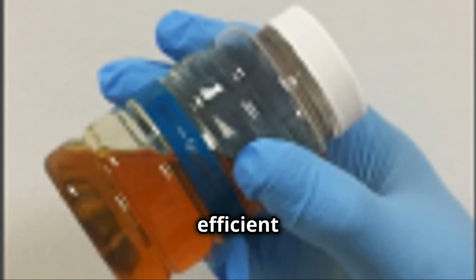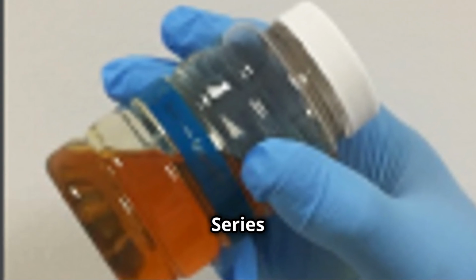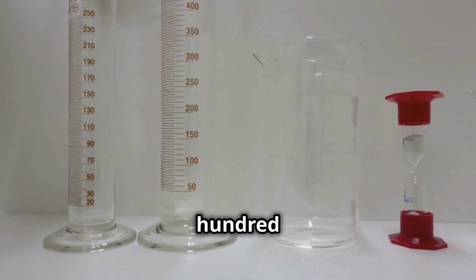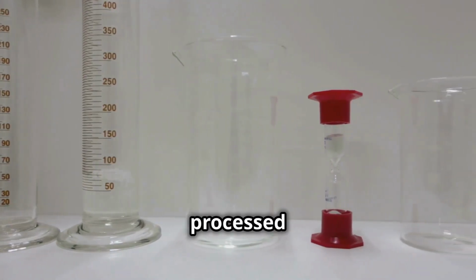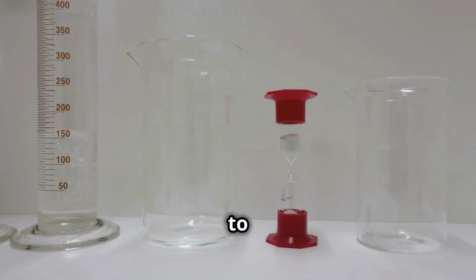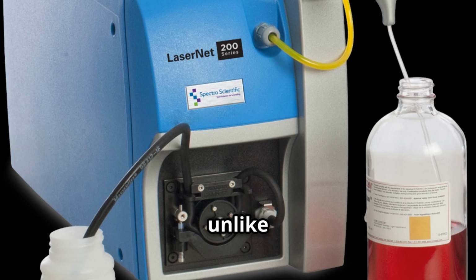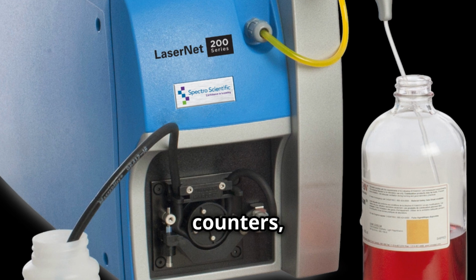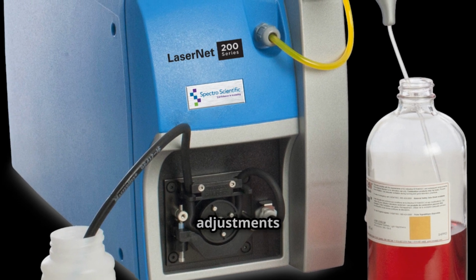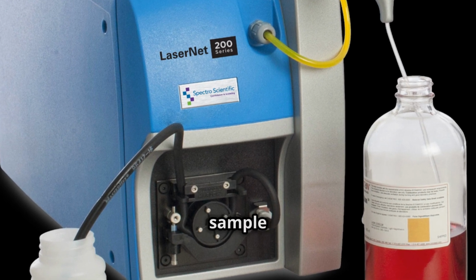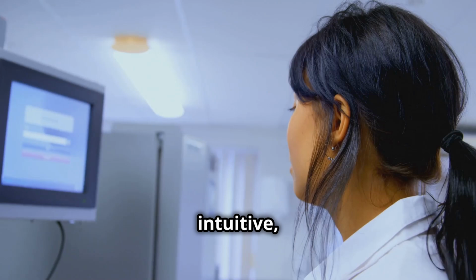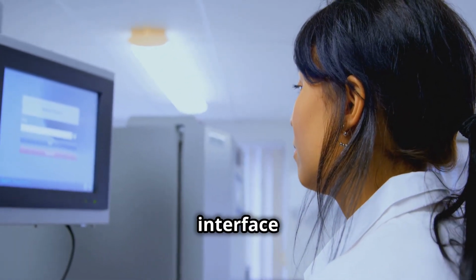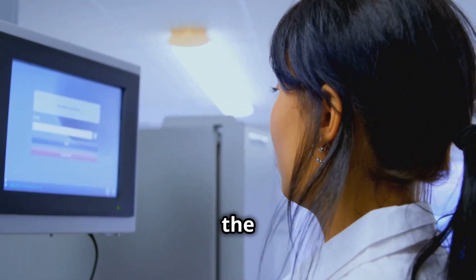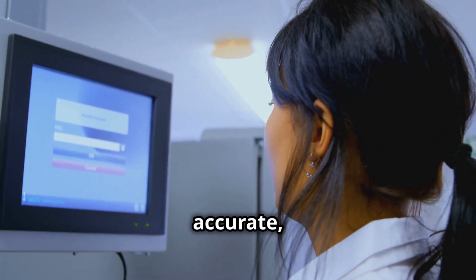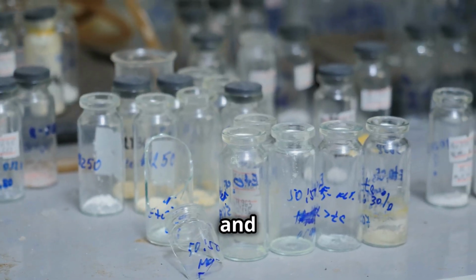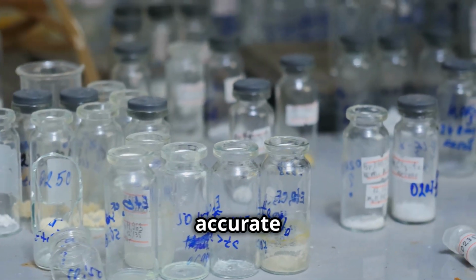Sample preparation is efficient with the LaserNet 200 series. Viscosities up to 320 centistokes can be processed without dilution due to the wide dynamic range. And unlike conventional light blockage particle counters, there are no flow control valve adjustments needed when testing different sample viscosities. With an intuitive, configurable graphical user interface and no calibration required, the LaserNet 200 series is fast, accurate, and easy to use. Proper labeling and organization of oil samples are crucial for accurate analysis.